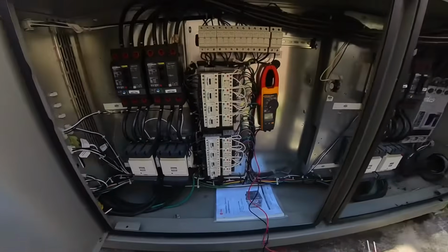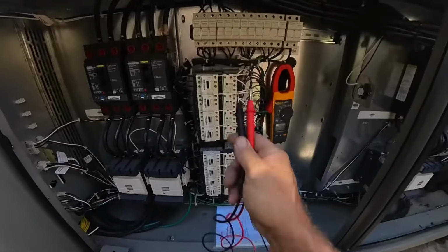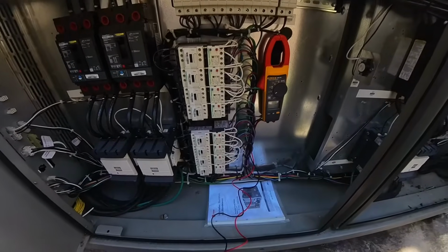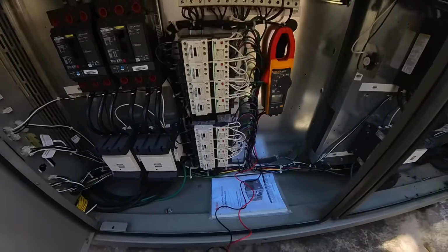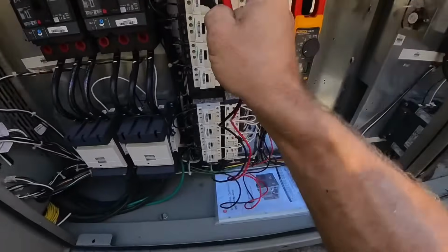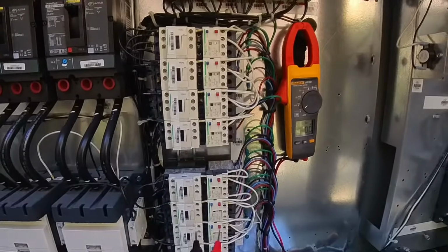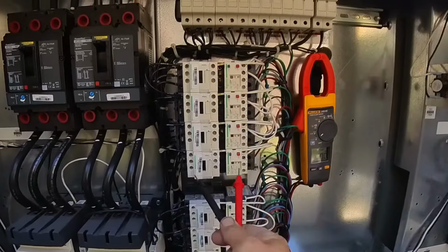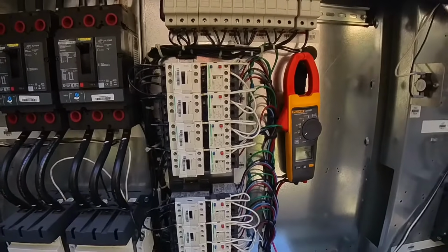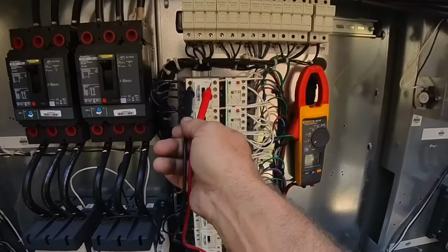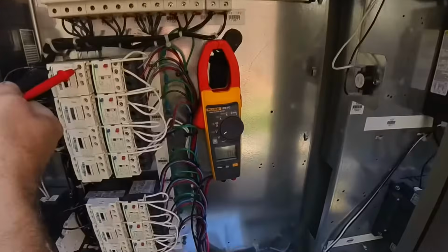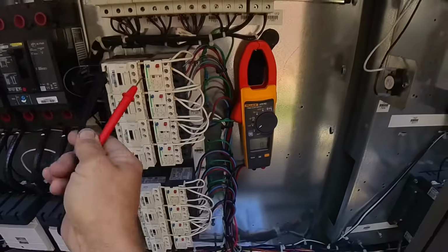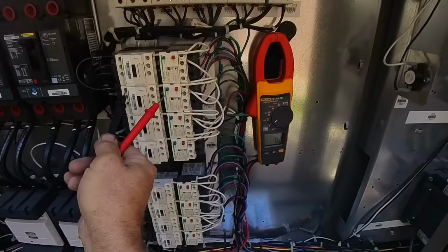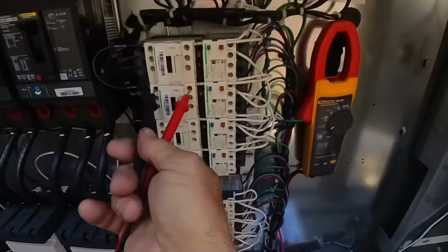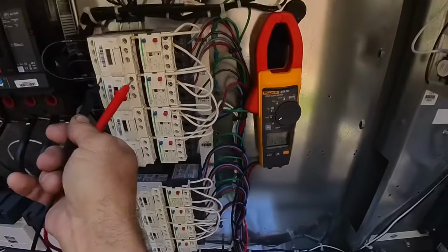Alright, so I got the control panel open here. These are all the contactors for the fan motors. And this top one is not pulled in. So I'm thinking these are circuit 2. And checking across the coil, I don't have 120 volts. Let's see this one down here across the coil. I do have 120 volts.